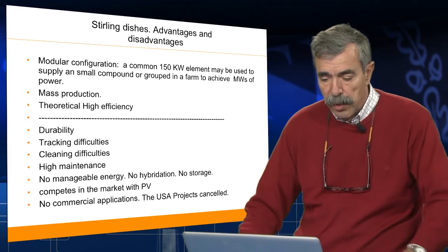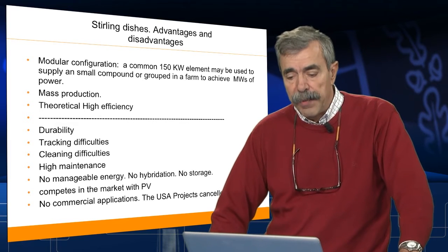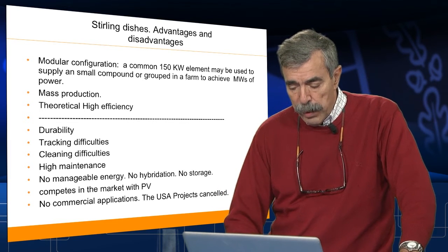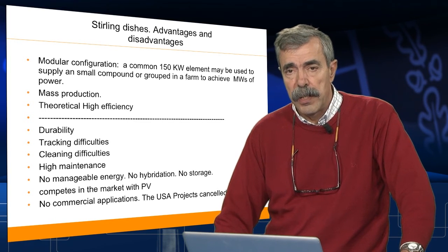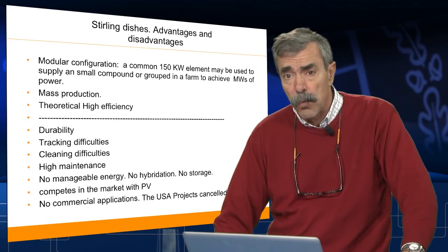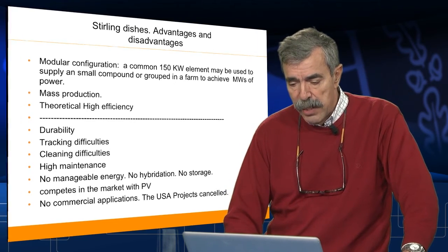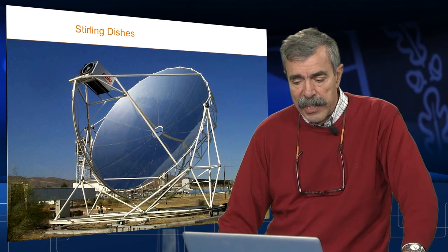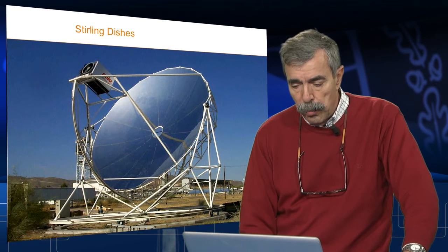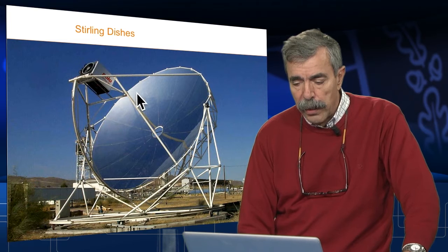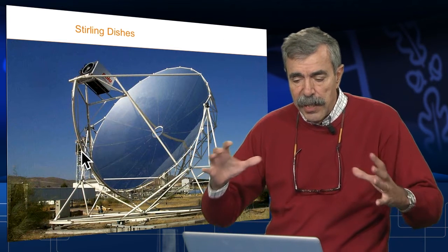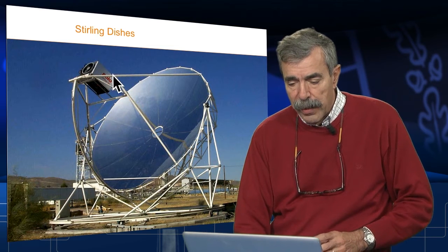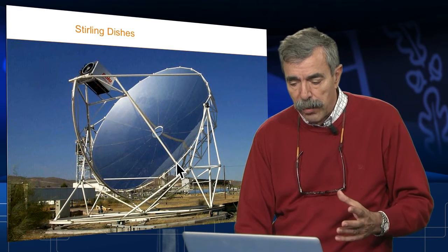On top of that, there are some cleaning difficulties. When you are operating a plant, cleaning is an issue. I mean, you have to be cleaning the solar field at least once per week. And imagine how to achieve an automatic mechanism to clean that surface properly when the surface is, let's say, hidden in between all these bars and all these systems.